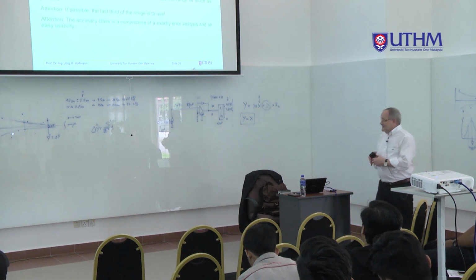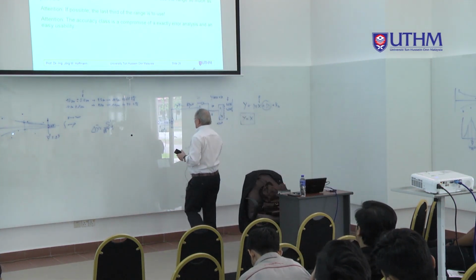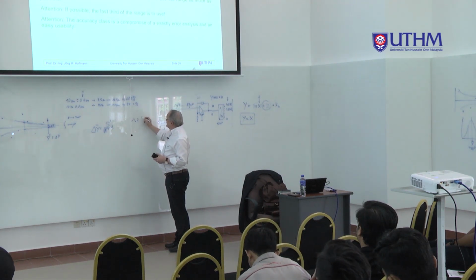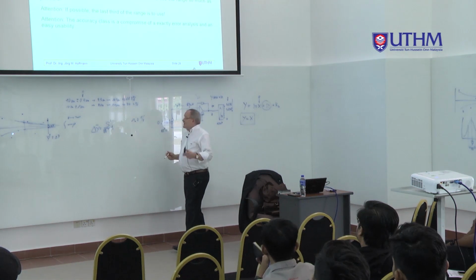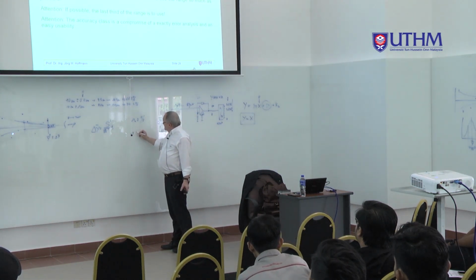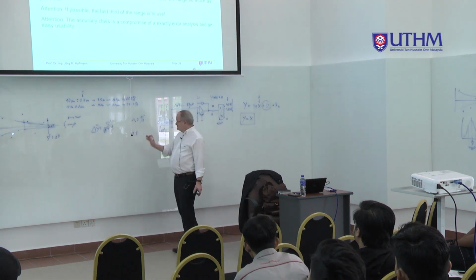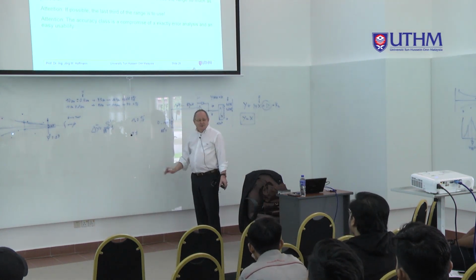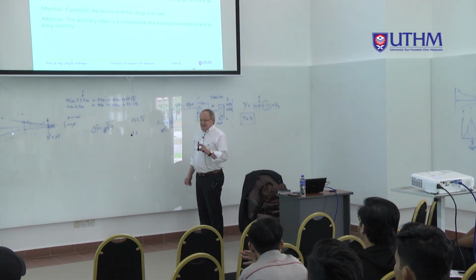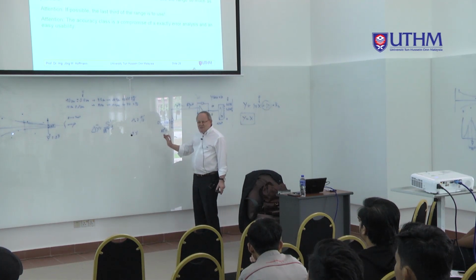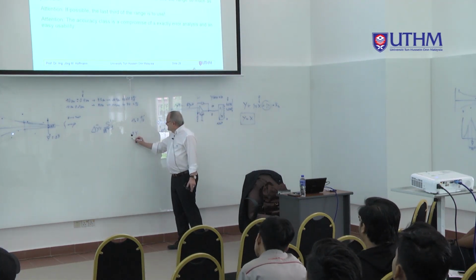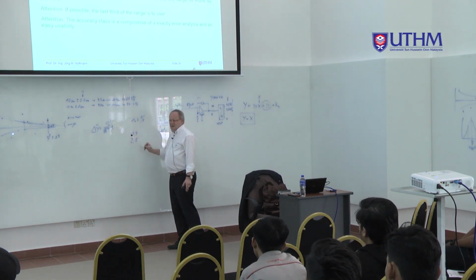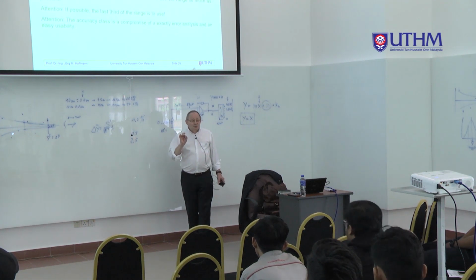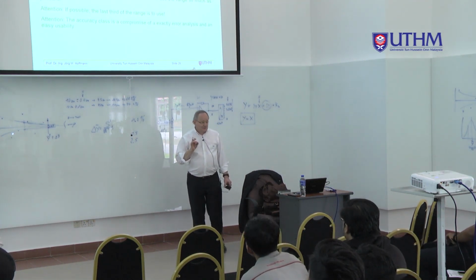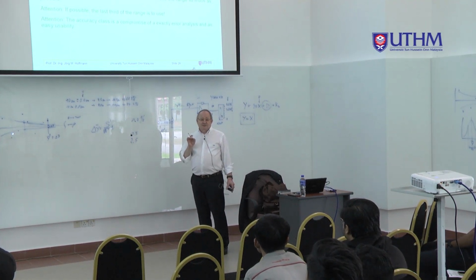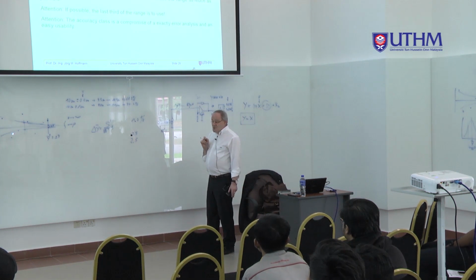When you have, for example, measured an error of 1.5%, one company says, I take the error class 1.5. We give a guarantee, 1.5%. Never will you measure a bigger error. Another company says, I'm not so really sure. For me, I can better sleep when I say 2.5 or 2. There is no rule, and therefore that is not a scientific method. But it is used very often in the industry. And you must look and pay attention.